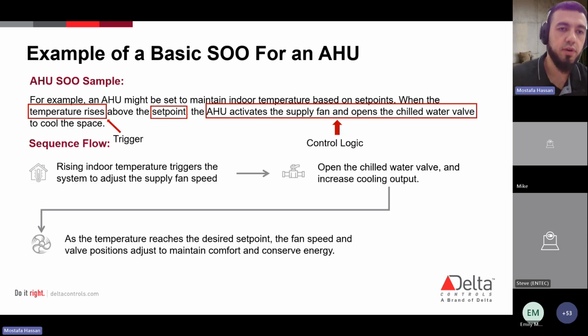So here's an example of a basic sequence of operation for an air handling unit. We're going to get a little bit more specific with the VAV later on, but we're just going to run you through the steps we mentioned, the control logic and things like that. So an air handling unit might be set to maintain indoor temperature based on set points, right? So let's read through this. So for example, the air handling unit is maintaining the indoor temperature based on set points. When the temperature rises, right, above the set point, we're going to stop here. There's your trigger, right? Your temperature rises, right?